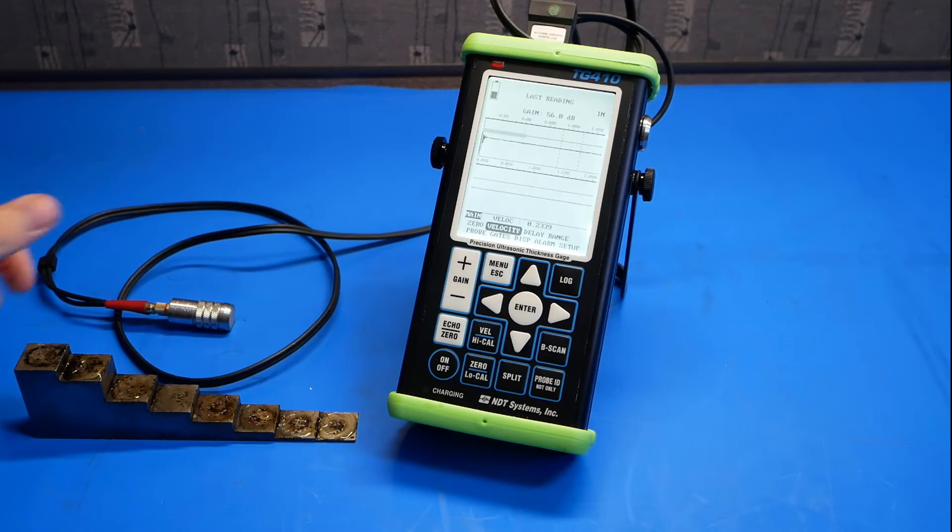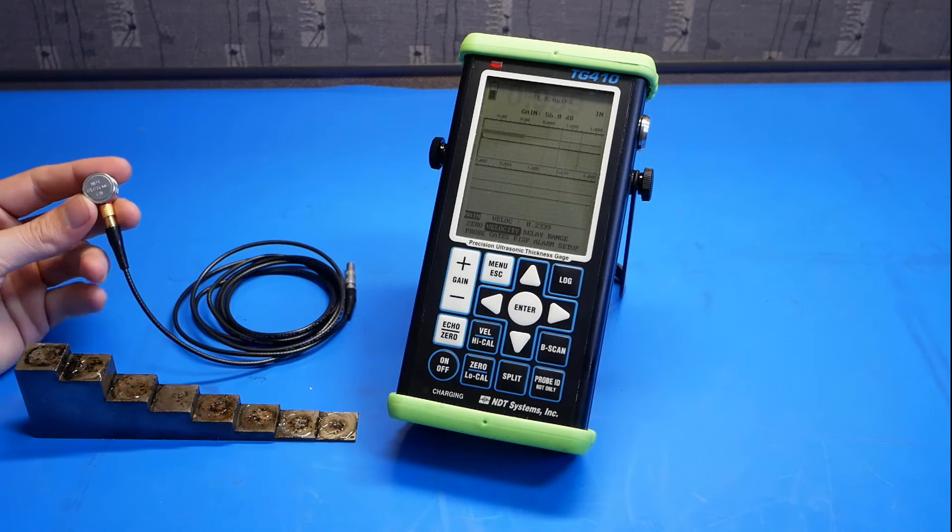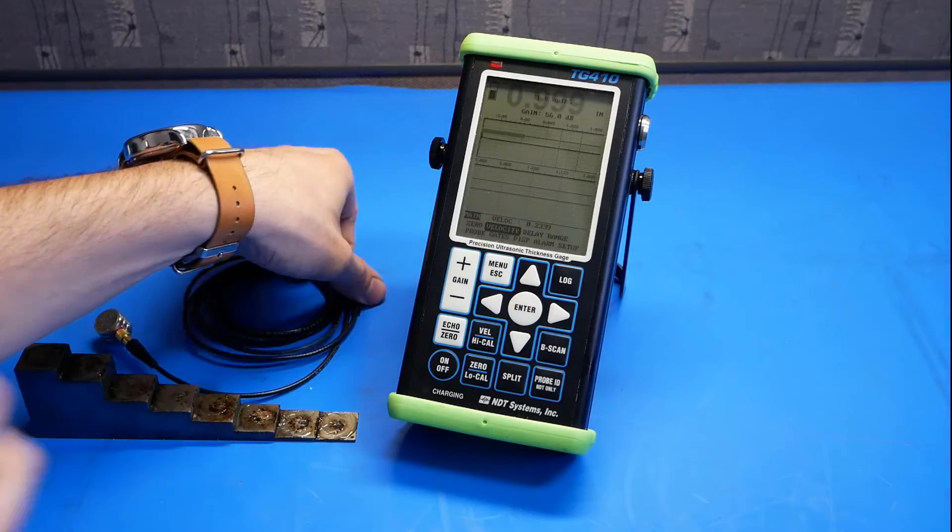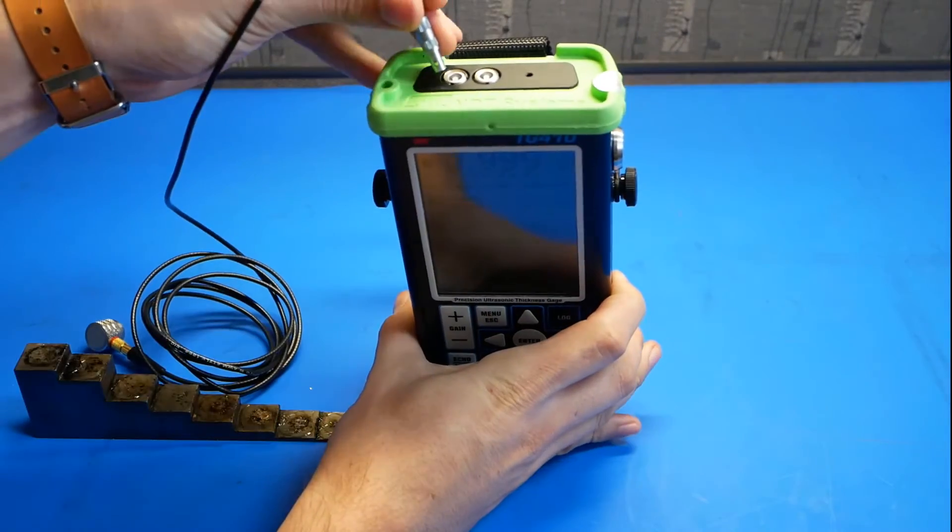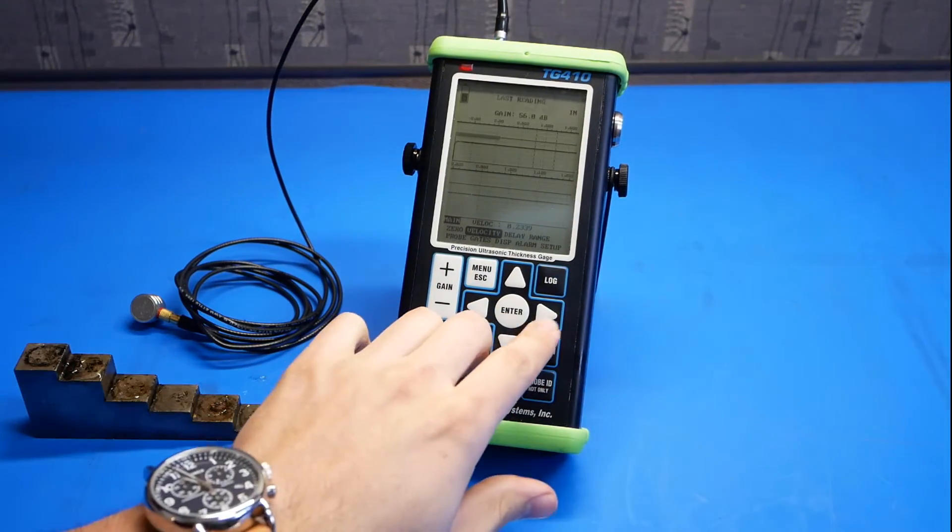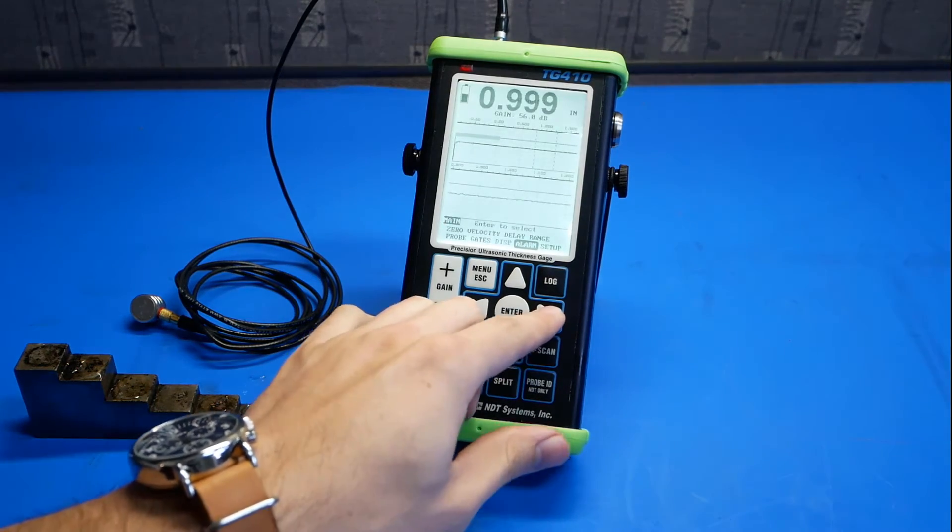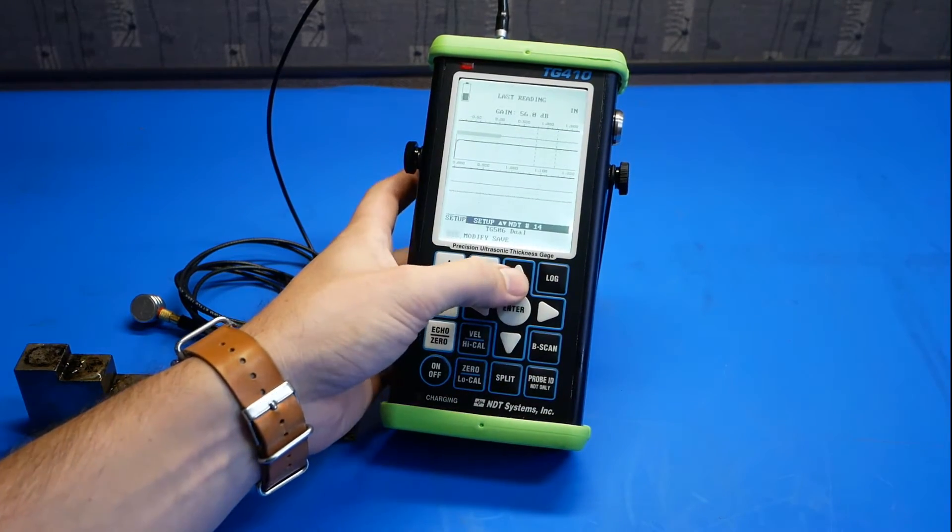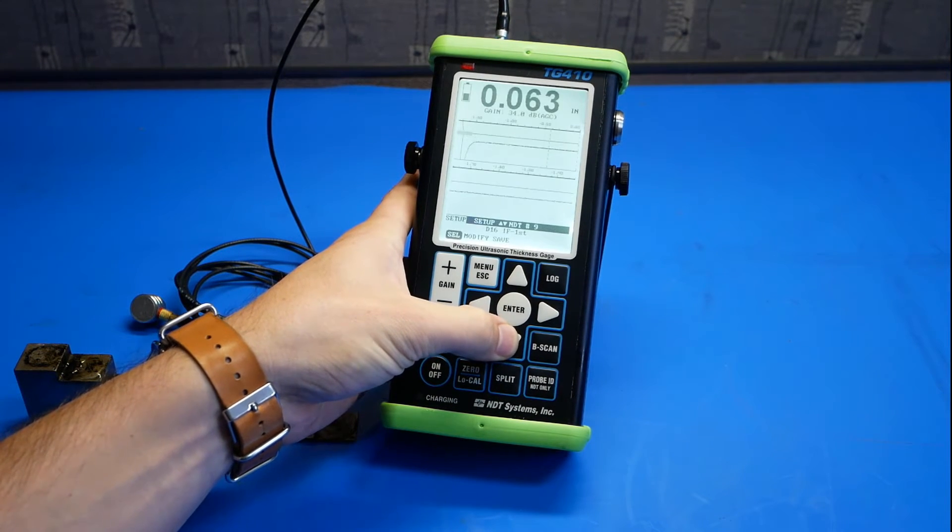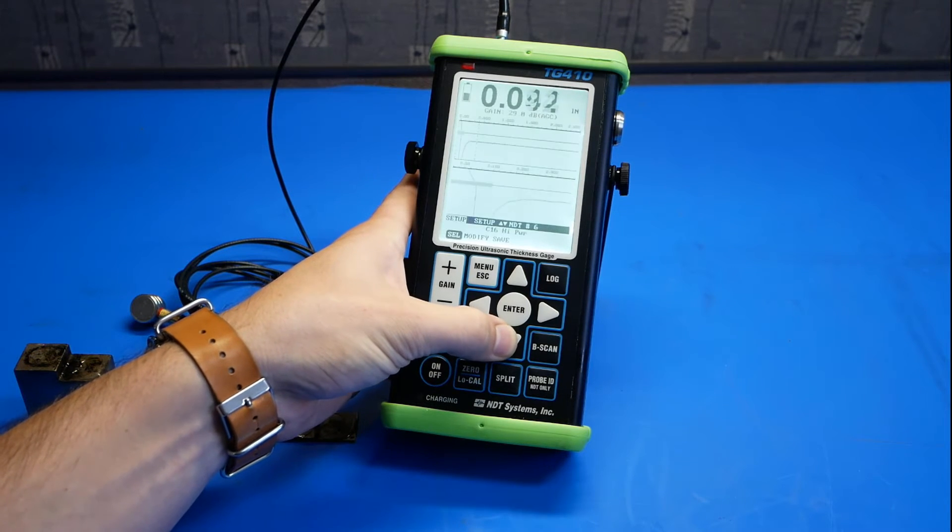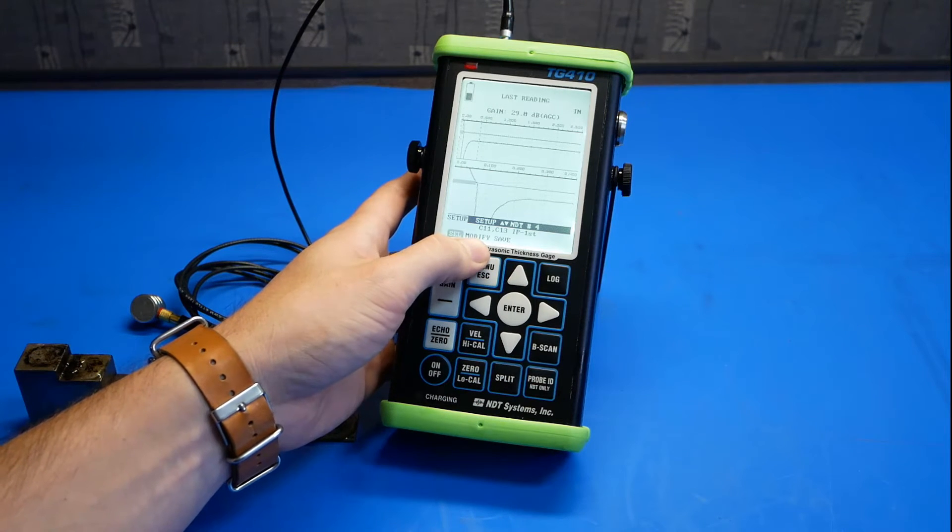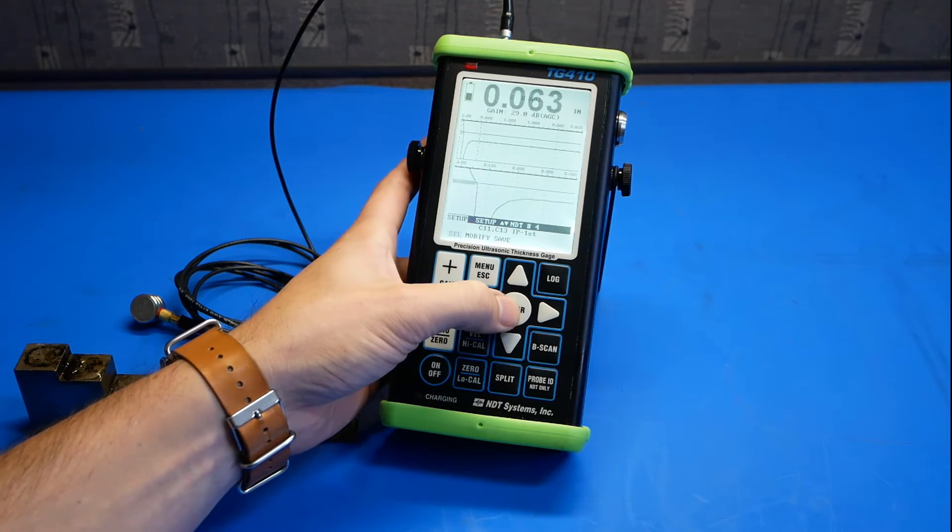Let's move on to the single element contact. Here we have a C11 contact transducer, also 5 MHz. We're going to plug it into the gauge to the leftmost socket. And then again, we'll go into the setup and look for the file. Once you've found the C11, C13 file, go ahead and hit select.